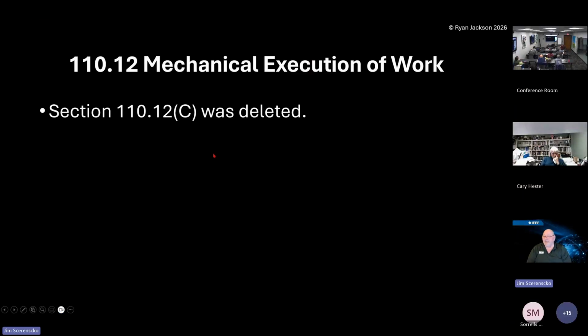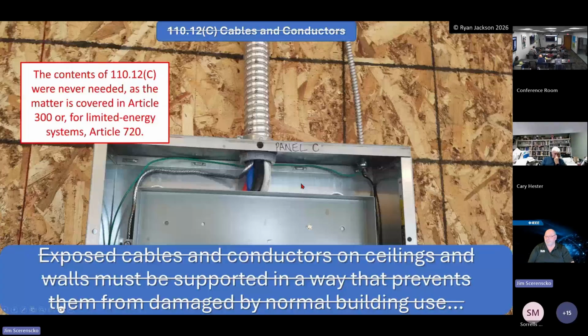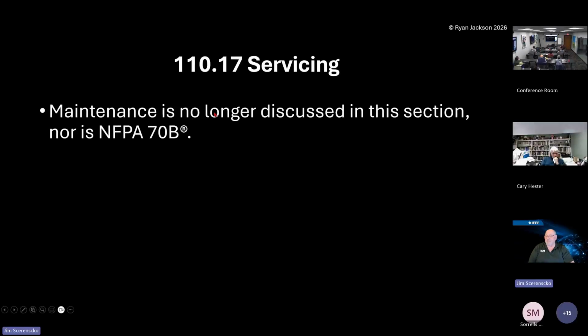They took out the mechanical execution of work. 110.12(C) was deleted. Exposed cables and conductors on ceilings and walls must be supported in a way that prevents them from damage by normal building use. That was never needed, as the matter is covered in Article 300. And for limited energy, it's covered in 720. So one thing got removed.